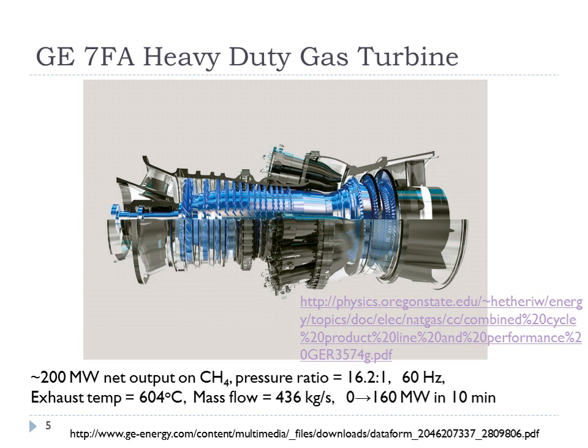Here's a picture of a General Electric 7FA heavy-duty gas turbine. I'm showing it with the compressor on the left, combustor in the middle, and turbine on the right. One way to tell these apart is that there will be more stages of compressors than turbines — that's an easy visual indicator, even though more power is generated in the turbine.